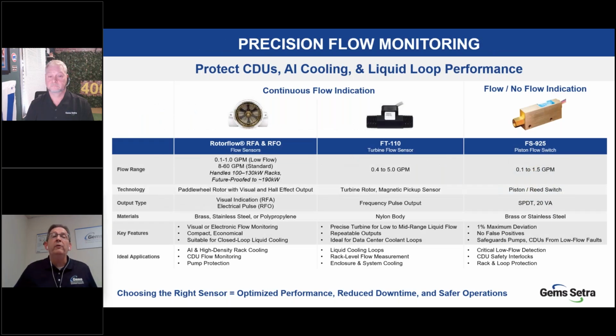So moving into the flow side, it really breaks down into two major categories: continuous flow indication, and then your on-off flow or no flow indication. And on the two left and center, we're utilizing the continuous side. The Rotorflow on the far left, as Dennis mentioned, is actually a product that could be visual only, although you're probably not opening the cabinet to look to see if flow is going. A pulse DC output, an analog output, and then actually conditioned to have a switch output if needed. These are for the higher set points and those larger racks, going up to the 130 kW rack.